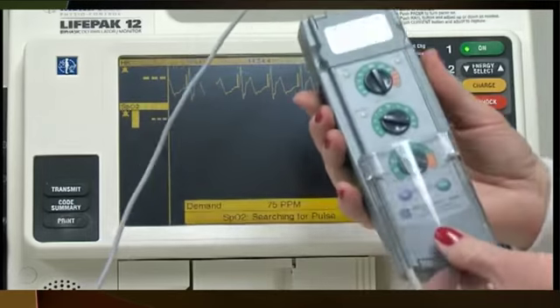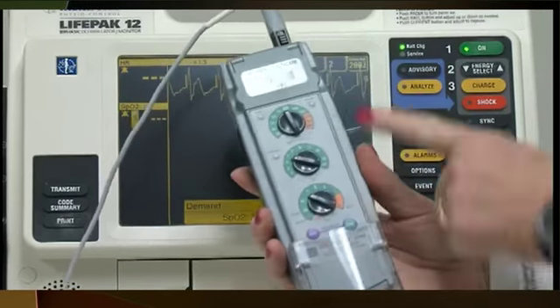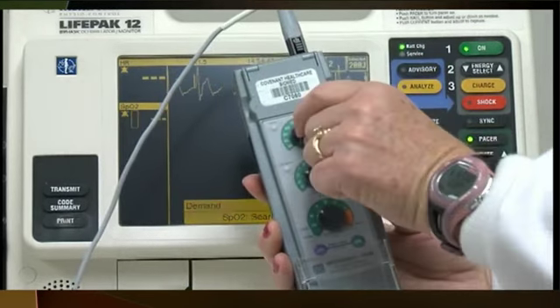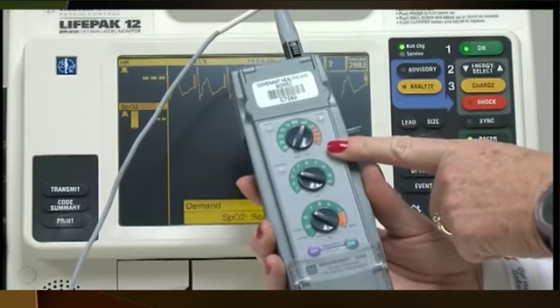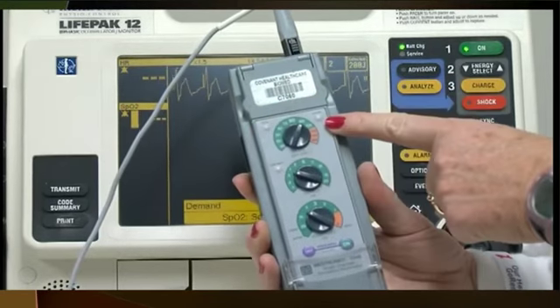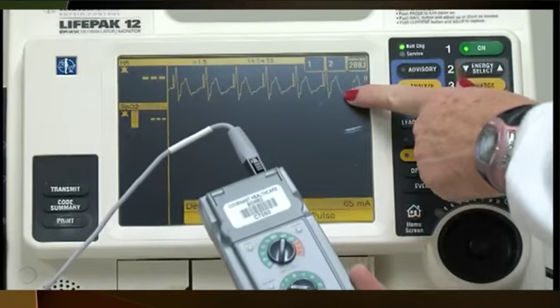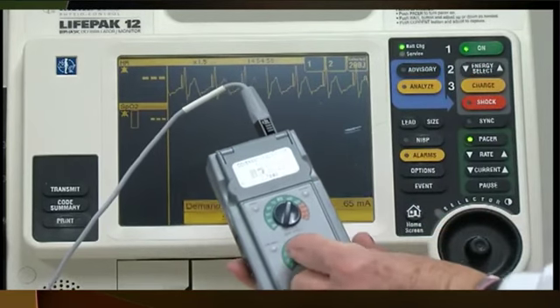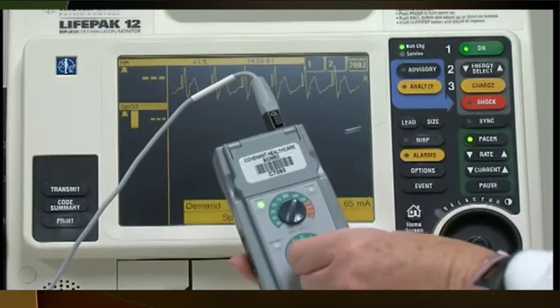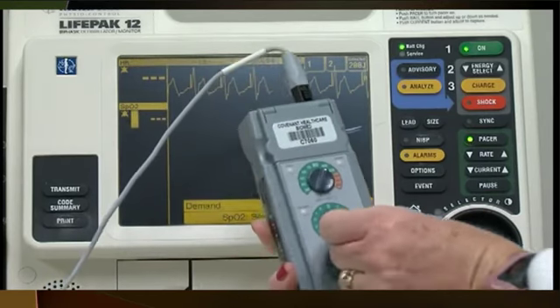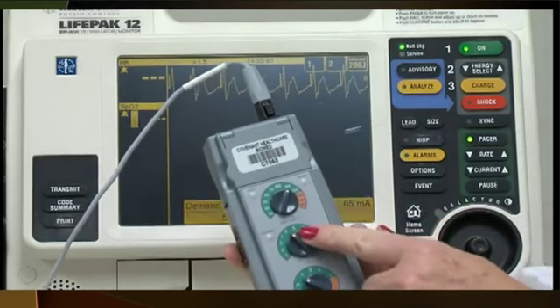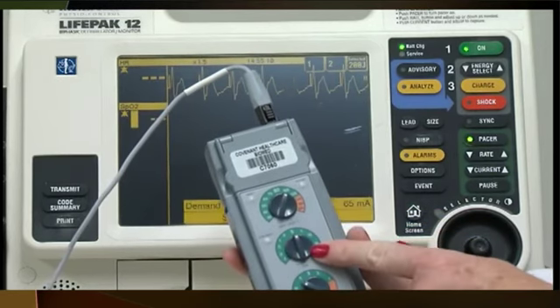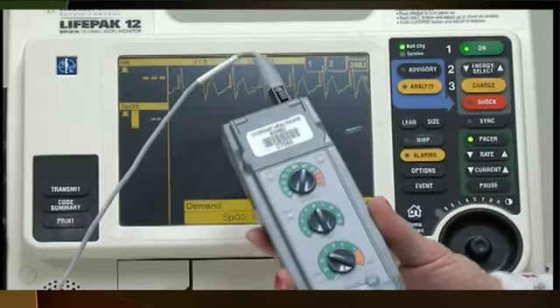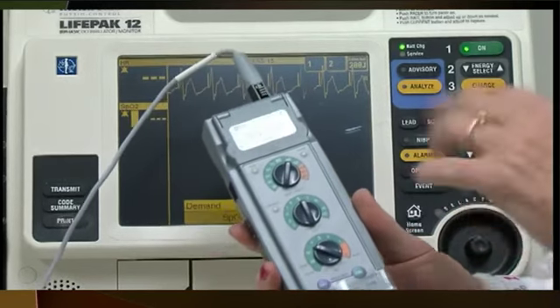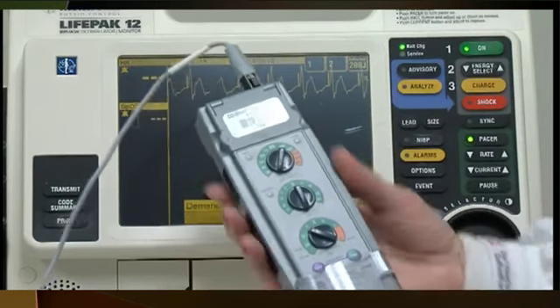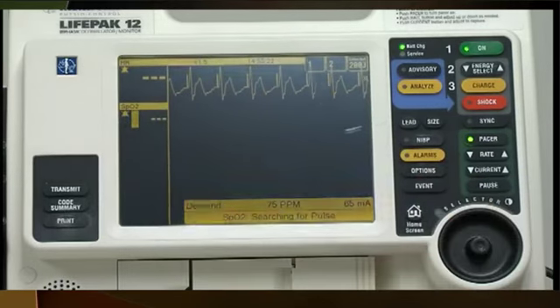Now with your internal devices that you use, the transvenous, this is going to be your rate. You're going to set that 10 or so above to get the one-to-one capture, and you're going to tell by the lights blinking if that's going to be one-to-one capture, and you can see it as we do here. This is your milliamp button that you will increase and decrease to figure out where your threshold is. If it was 2, I need to set it to about 4 or 5 for my patients, so that way they make sure that the tissue is stimulated and you have good contraction or reaction from that. And then make sure to close up your pacemaker.